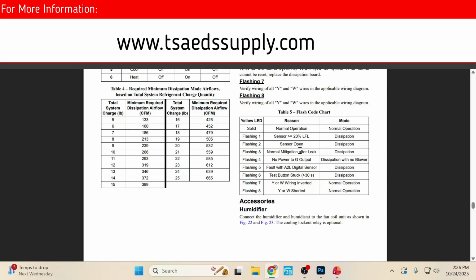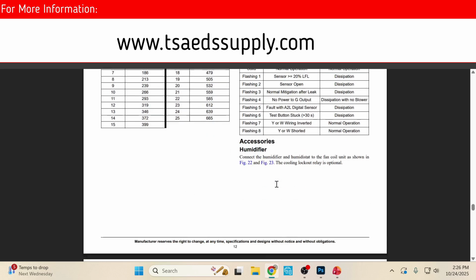There's a timer on this. When it senses a leak, it's going to blow, and that's in this manual. You'll have to see where it's at, and you'll see this right here. You have to have a required dissipation CFM. So if you have 7 pounds of refrigerant in it, you have to make sure you have at least the right amount of CFM to discharge all that through the ductwork.